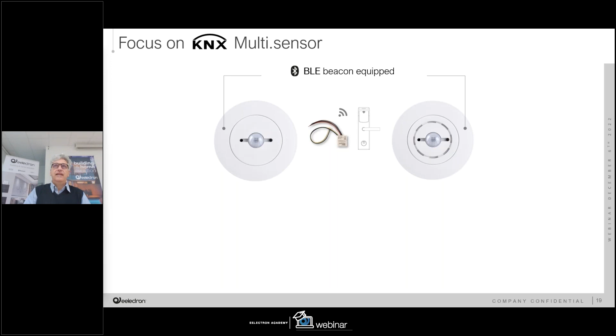Let's look a little deeper at what we mean by e-lock interface. It's a small module that can interact with door lock systems from third parties to gather events like the opening or closing of a door, and also to understand if it's the guest entering the room or the housekeeper. This small interface device talks wirelessly with the third-party door lock system, and it has to be connected to one of our presence detectors or multi-sensors, either version 1.3 or 03.